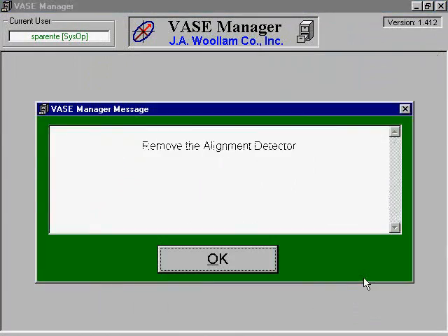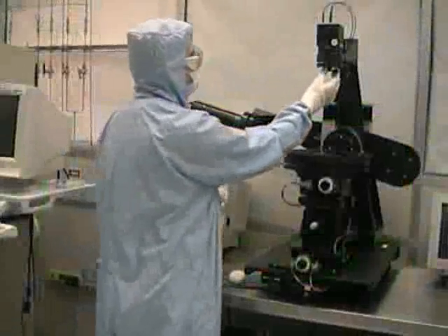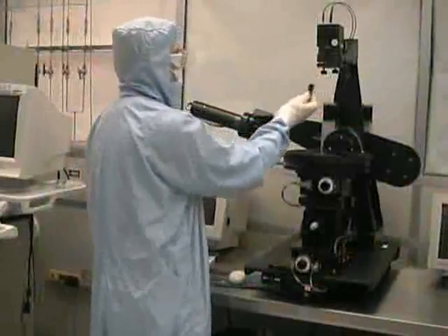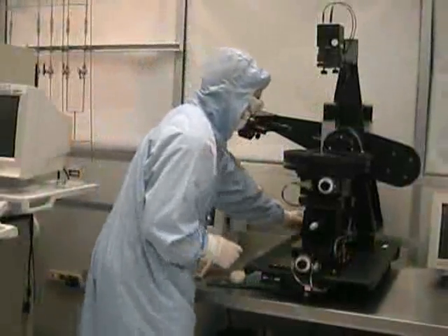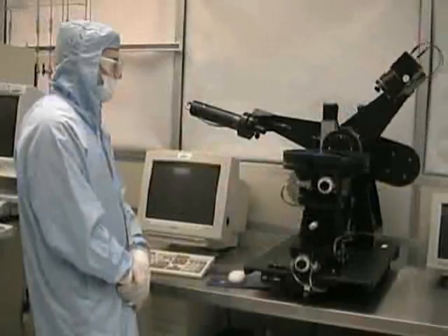You should then be prompted to remove the alignment detector. Once you have done this, select OK. The polarizer will then move into the scan position.